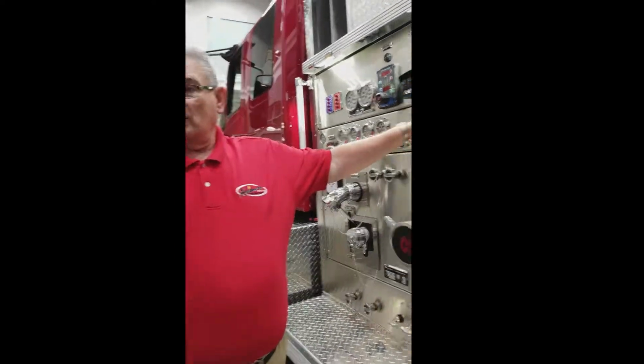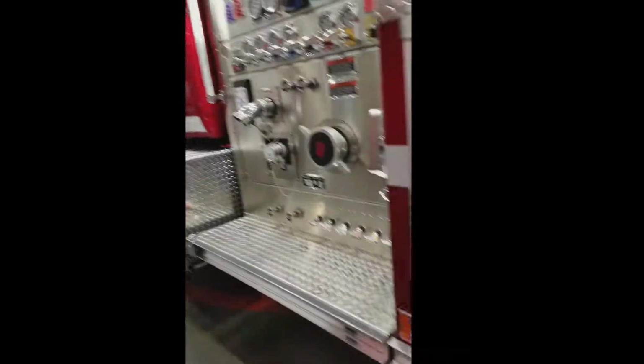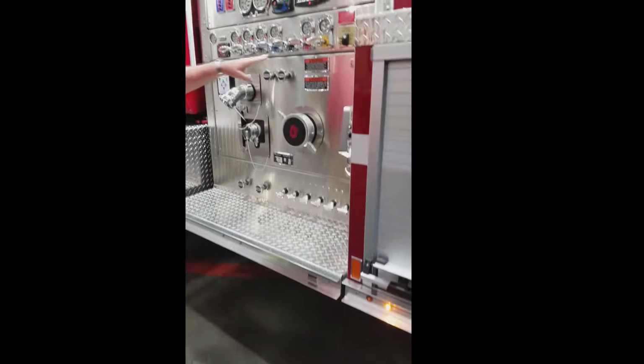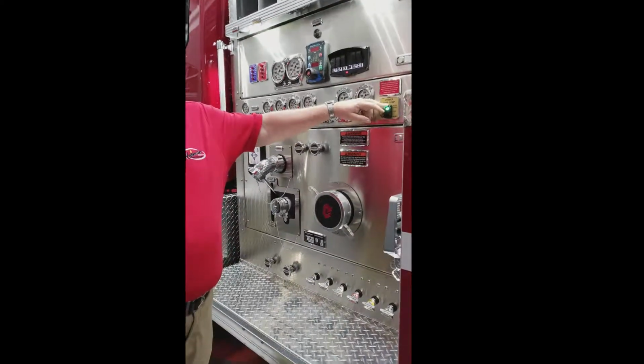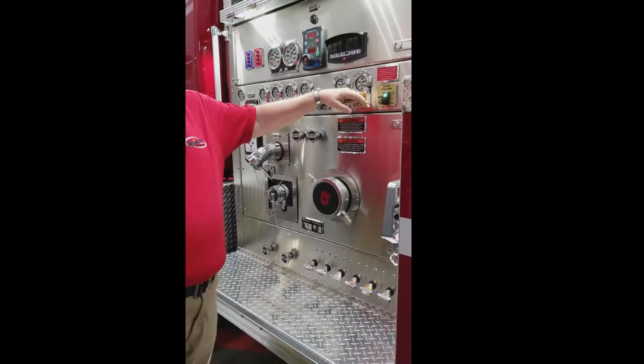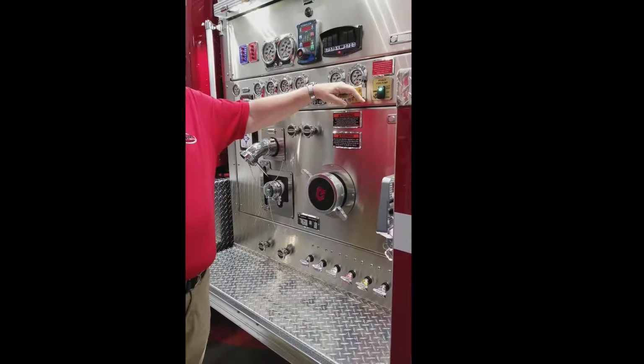But if you run it, it's kind of like, I know when I was up in North Dakota, we had to drain everything and run air through them, and same thing here. Okay. Get the pump dry, so kind of the last thing you do, shut your main drain, shut your drains before they leave the firehouse, spin that for 10 seconds. That makes sure it's just that air in what's there. Is that dripping out down there? Yeah, because I opened the drain. Yeah. And your main drain is up underneath. So for the most part, leaving it there is okay. It really is.